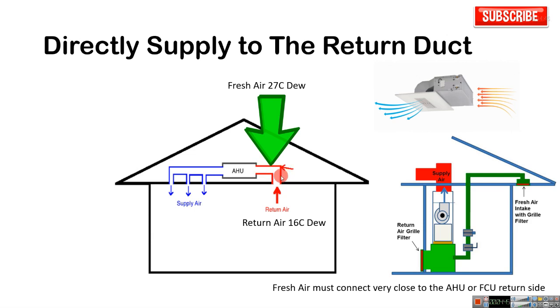You can see water droplets at the return air diffusers if the connection is not close enough. You must connect the fresh air duct very close to the return side of the FCU. This is the return side of the FCU — connect very close to it. Then any condensate water will be removed through the condensate drain.